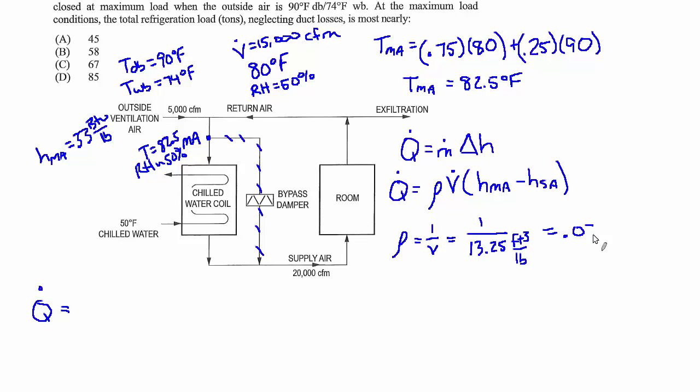Now we're ready to make the substitution. So 0.075 pounds per cubic foot for the density times the volume flow rate, 20,000 CFM times 60 minutes in an hour—don't forget that. Gets rid of minutes, also gets rid of feet cubed. And now the difference in the enthalpy across the coil.